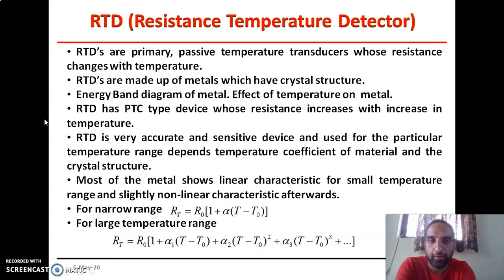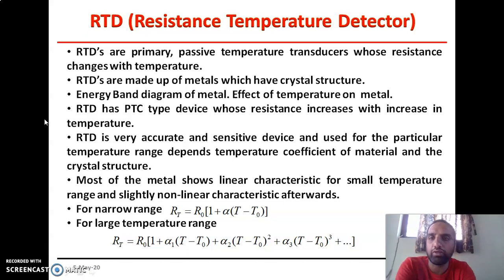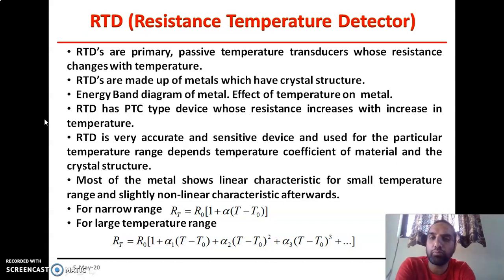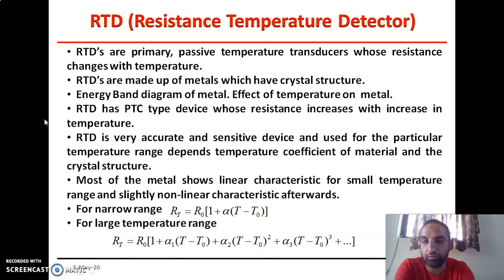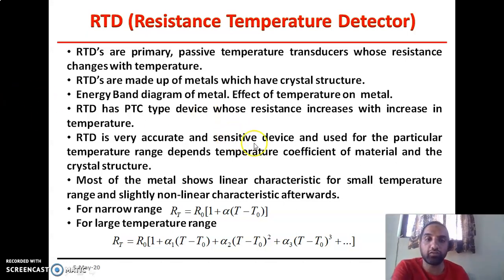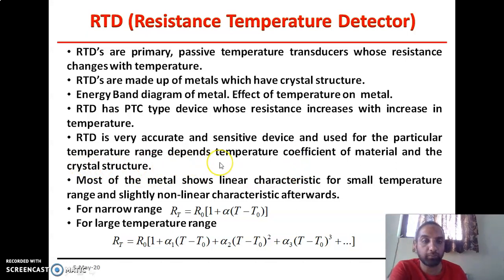What will happen if we increase the temperature? If we increase the temperature, the collision of electrons also increases, because the thermal excitation affects the electrons present in the metal — the vibrational amplitude keeps increasing, and because of that they collide more frequently, giving more resistance. So this is the effect of temperature on that metal. RTD has a positive temperature coefficient — PTC type. It is called PTC because its resistance increases with increasing temperature. RTDs are very accurate and sensitive devices, used for a particular temperature range depending upon the temperature coefficient of the material and crystal structure.